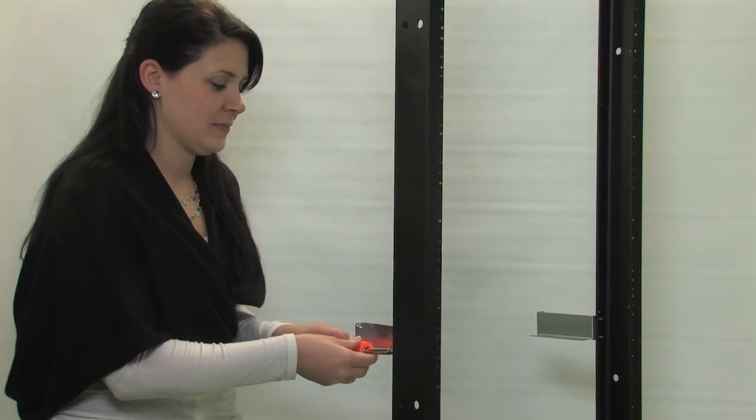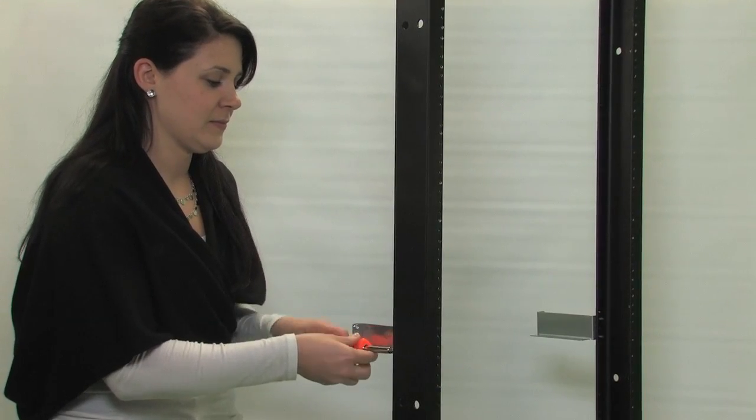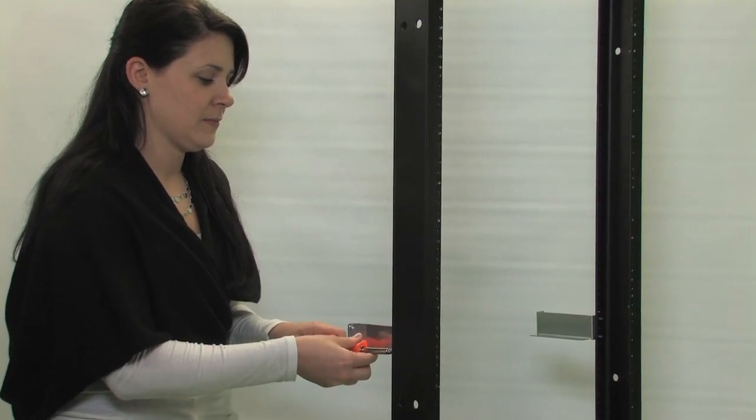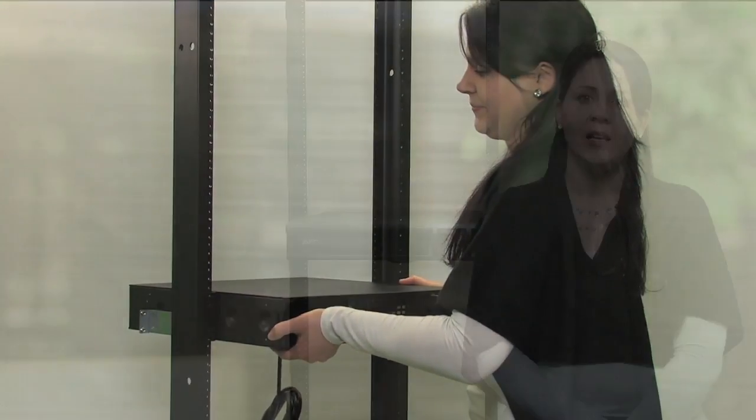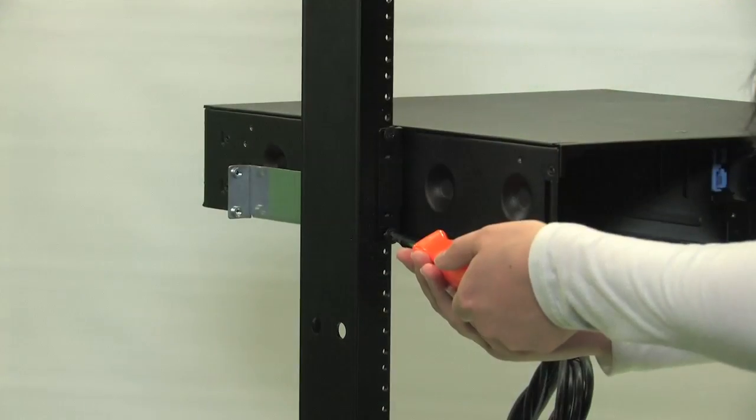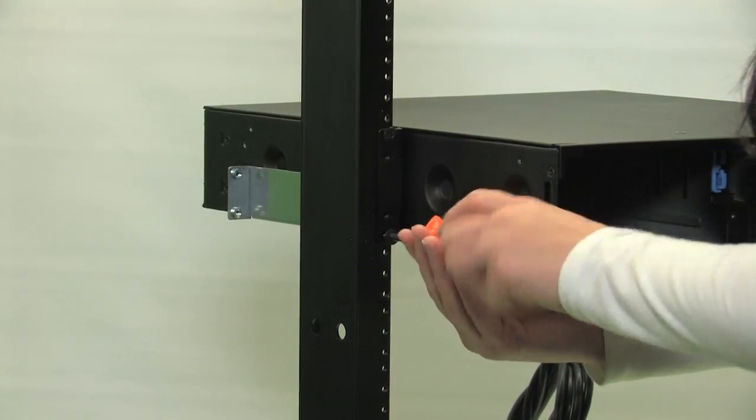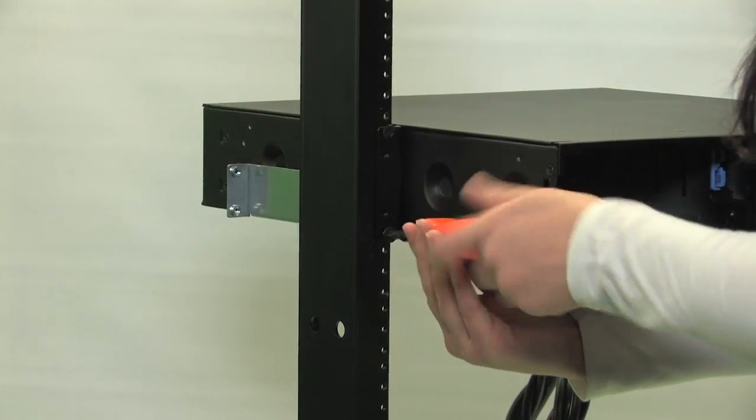Determine your desired U position and attach the bracket to the rear side of the rack. Now slide the UPS onto the supported brackets and secure the UPS to the front of the rack using the thumb screws provided.